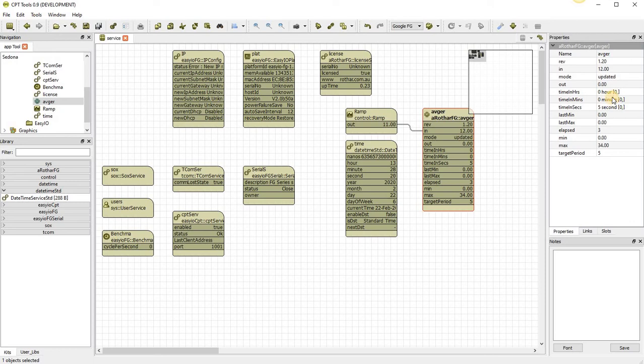So if we set our time to we want to average every 6 hours, it will only update every second instead of every scan, instead of 5 times a second or whatever you've got your scan set to. This 6 hour will line up at midnight, 6 AM, midday, 6 PM. So that at midnight, at the end of each day, you get a value being saved to the database or to your history log.